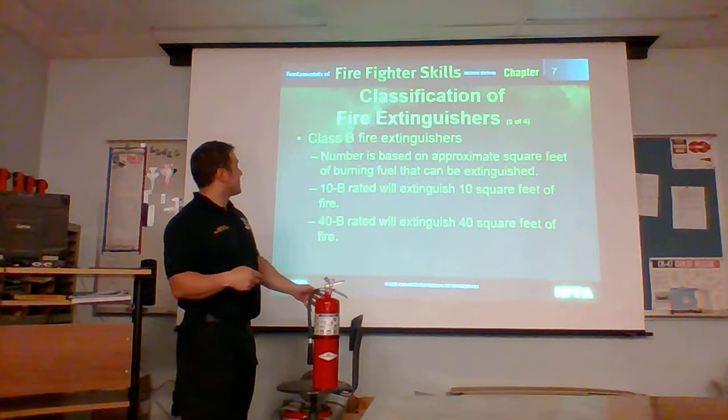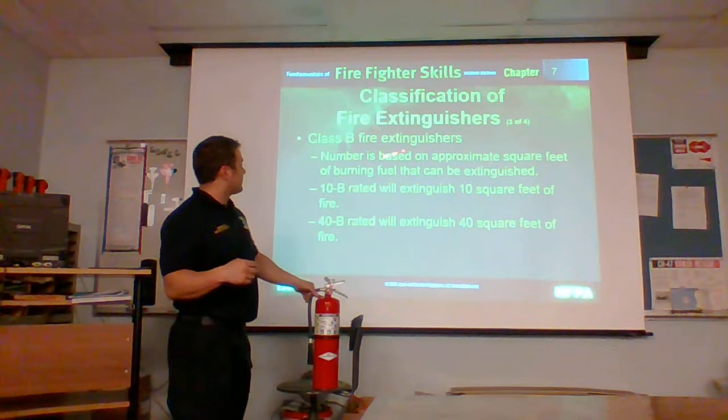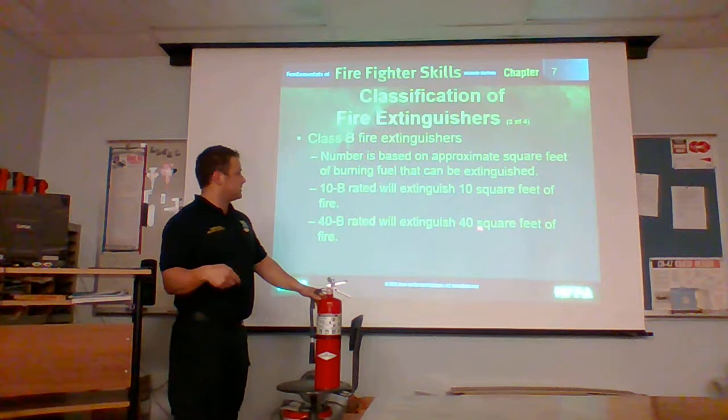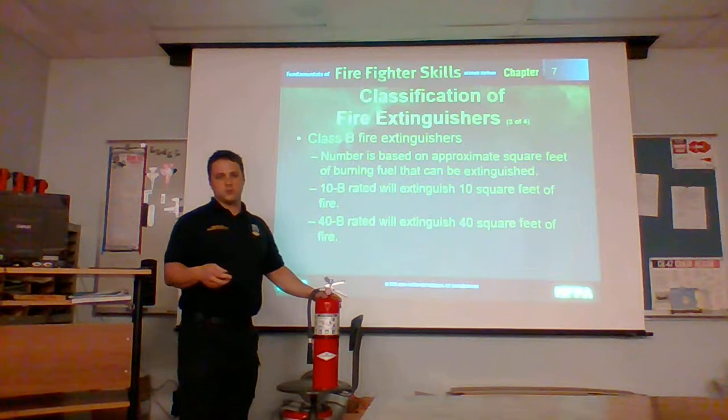We're going to go on to Class B fire extinguishers. The number is based on approximate square feet of a burning fuel that can be extinguished. A 10B rated would be 10 square feet of fire — not very big, kind of a small trash can of fire. A 40B would be 40 square feet of fire — a little bit bigger.